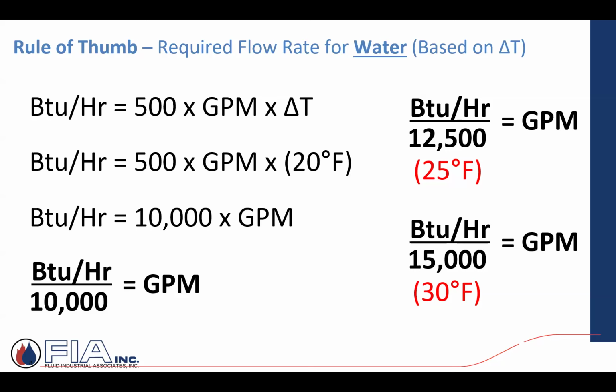My terminal units that are out there now need to be configured for a much lower average water temperature. So I can take it to the extreme, and depending upon what I'm feeding, a terminal unit, a fan coil, radiation, baseboard, whatever the case may be, radiant floors, makeup air coil. If that temperature drop gets very excessive, the BTU output at that lower temperature could have a negative impact. If I can account for that by having an oversized heat exchanger, heating surface area for the lower water temperature, I can do that. But a lot of times the amount of surface area that you would need offsets the benefit of using the smaller pump, the smaller diameter pipe, because the flow rate's lower. I'm compensating with other things, so it's kind of like a trade-off.